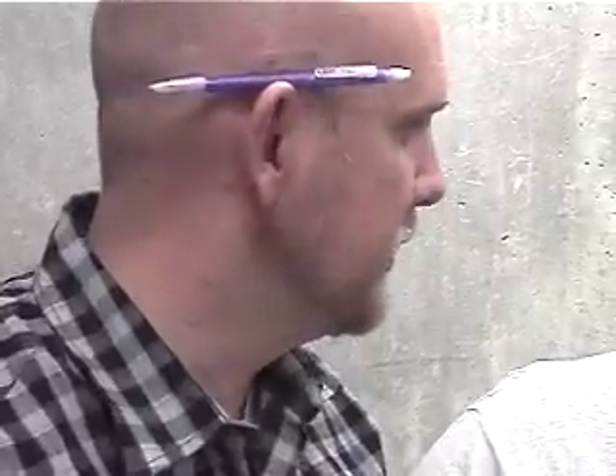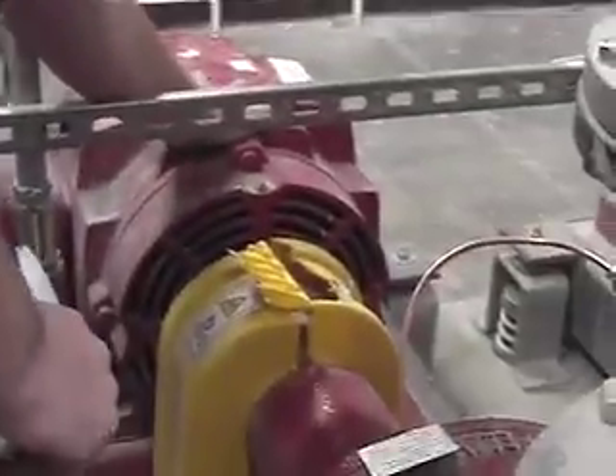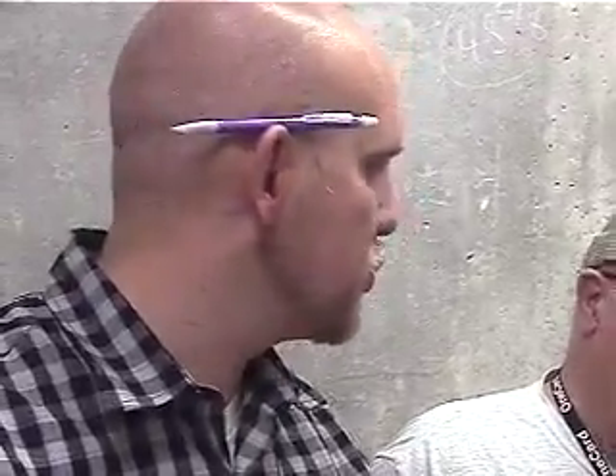So again, it's very simple to maintain these things. They kind of go into extra detail on this. They do say every month you want to come and just inspect it. The main thing with a pump is to visually inspect it. Make sure you feel the motor, see if you feel any extra vibration. Feel the air, make sure air is coming out. You want to see if it's extra hot. Just do a visual inspection. So you'll be checking for vibration, for temperature, checking for leaks, seeing if there's water dripping anywhere. Obviously, those are signs of problems.